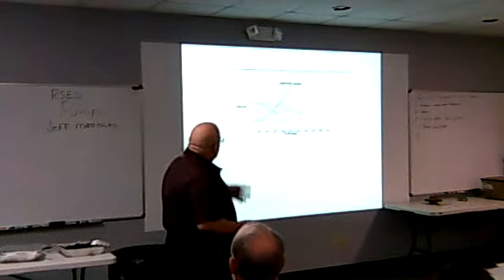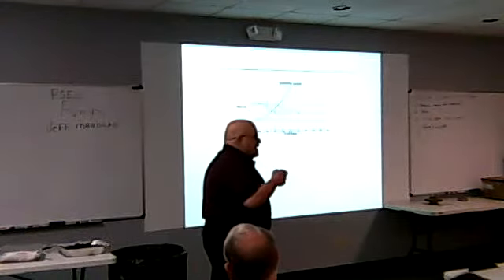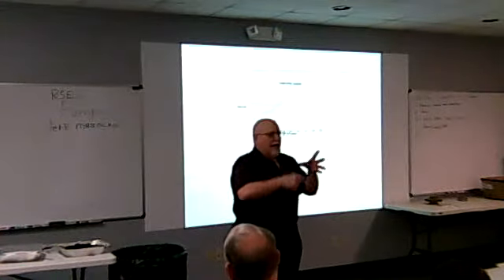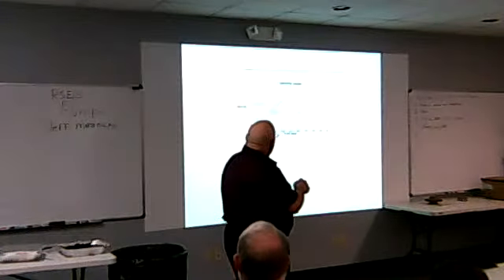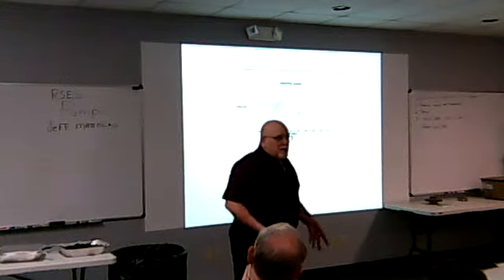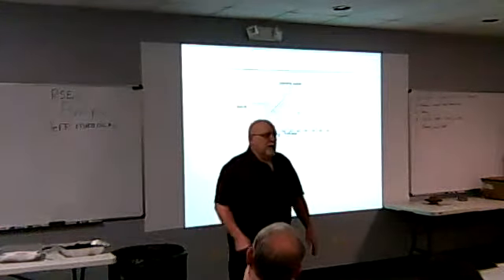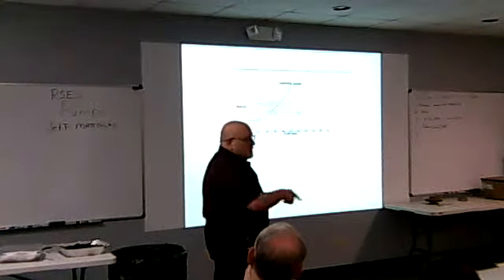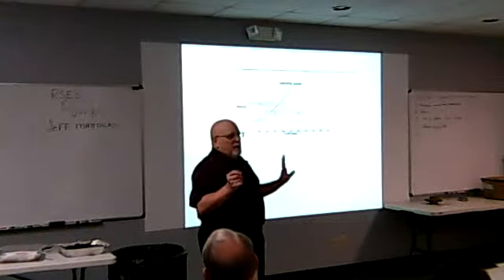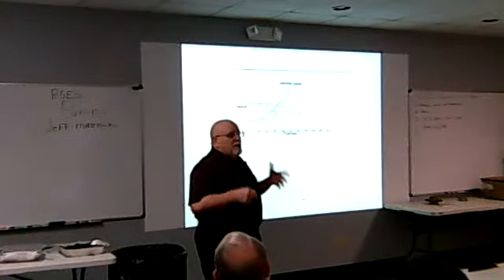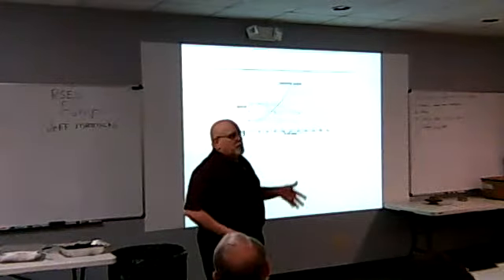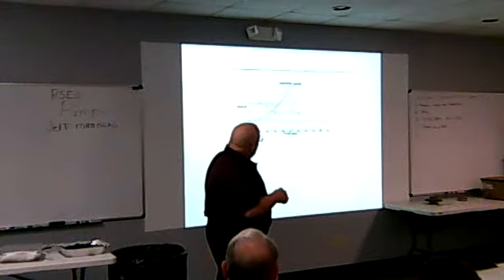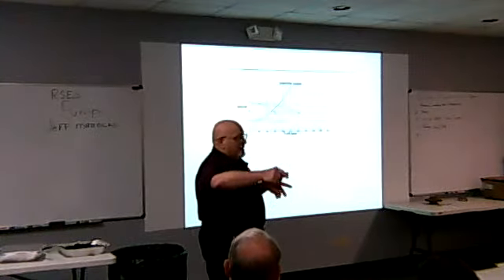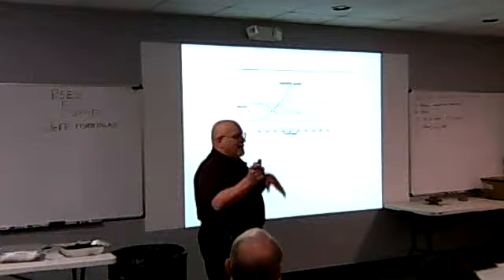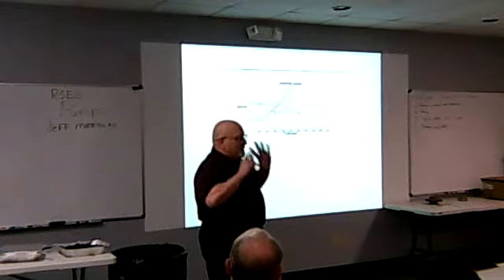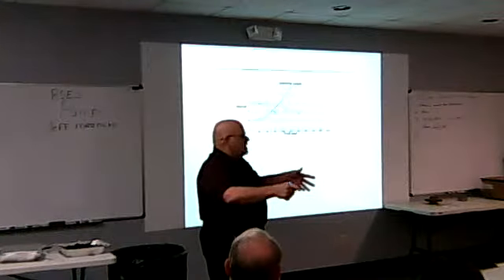Okay, this is important too. When we're doing pumps in parallel, pumps in series always stack the head, just like our vertical turbine and added head. Centrifugal pumps, you can deadhead. Positive displacement pumps, you cannot do that. They will blow themselves up. I can take a typical pump like this impeller, throttle it to nothing and let it spin. It will develop heat over time, it could damage it, but for small times, it's just going to slip and keep spinning. But when we make a series selection, every pump will add head, and the flow will be constant. It's like an electrical circuit. Parallel versus series: in series, the voltage stacks; in parallel, you split the flow and have the same head.